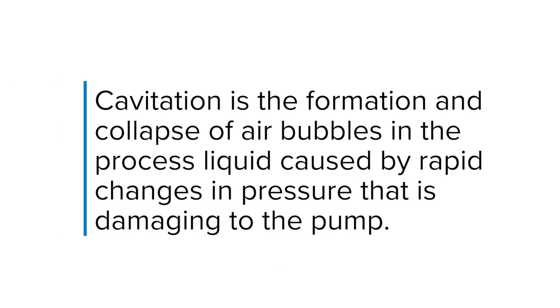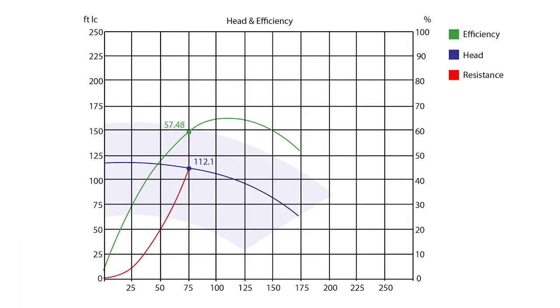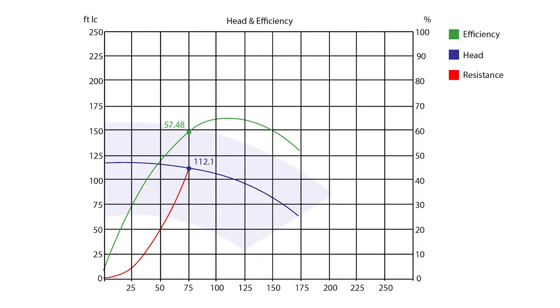Cavitation is the formation and collapse of air bubbles in the processed liquid caused by rapid changes in pressure, which is damaging to the pump. Pump curves also show you where pumps operate at maximum efficiency. In general, the center point of a curve indicates the head and flow coordinates where a pump is operating at maximum efficiency.